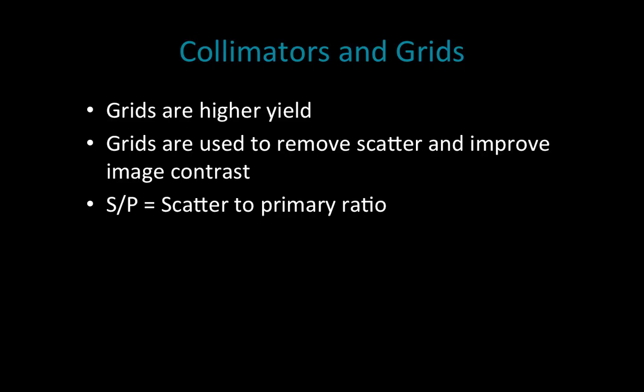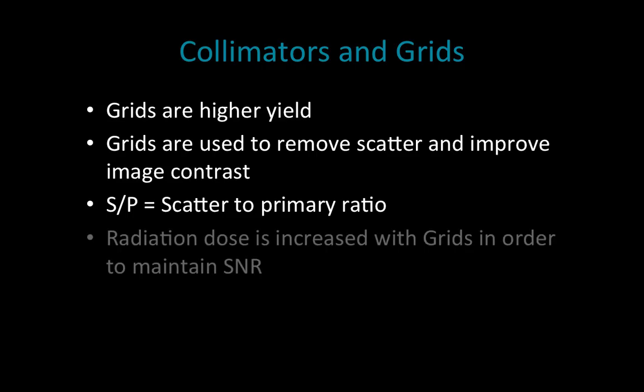Different from filters, grids are placed behind the patient — so the x-ray has already gone through the patient, and before reaching the image detector, the grid is there to block any photon that has deviated from its primary path, namely scatter. The scatter-to-primary ratio is a metric we'll see is very important for image contrast in a moment.